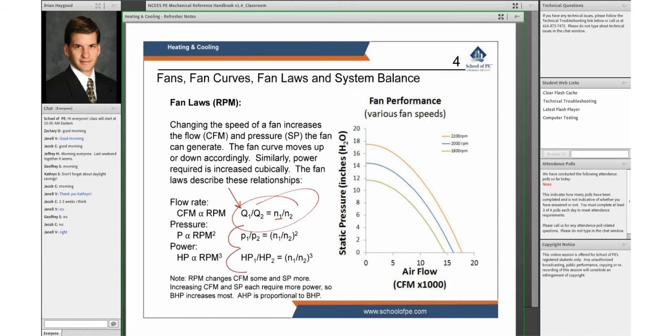We can say that the cubic feet per minute of air flow rate is proportional to the RPM, and we could write this equation as putting parentheses here and putting a one exponent there and a one exponent there. So if we increase the RPM we get a corresponding increase in flow rate. But if we increase the RPM, the resistance to flow, which is the pressure generated against that flow, is also going to increase and it turns out that increases with an exponent of 2.